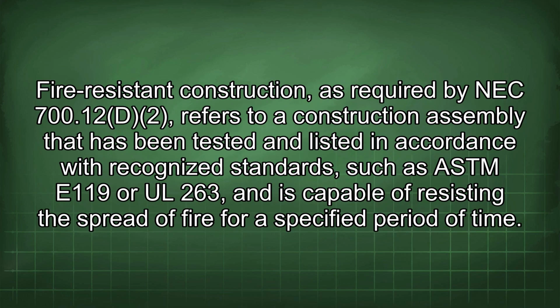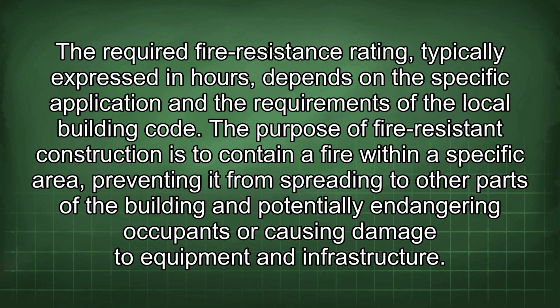Fire-resistant construction, as required by NEC 700.12 D2, refers to construction assembly that has been tested and listed in accordance with recognized standards such as ASTM E119 or UL 263, and is capable of resisting the spread of fire for a specified period of time. The required fire resistance rating, typically expressed in hours, depends on the specific application and the requirements of the local building code. The purpose of fire-resistant construction is to contain a fire within a specific area, preventing it from spreading to other parts of the building and potentially endangering occupants or causing damage to equipment and infrastructure.